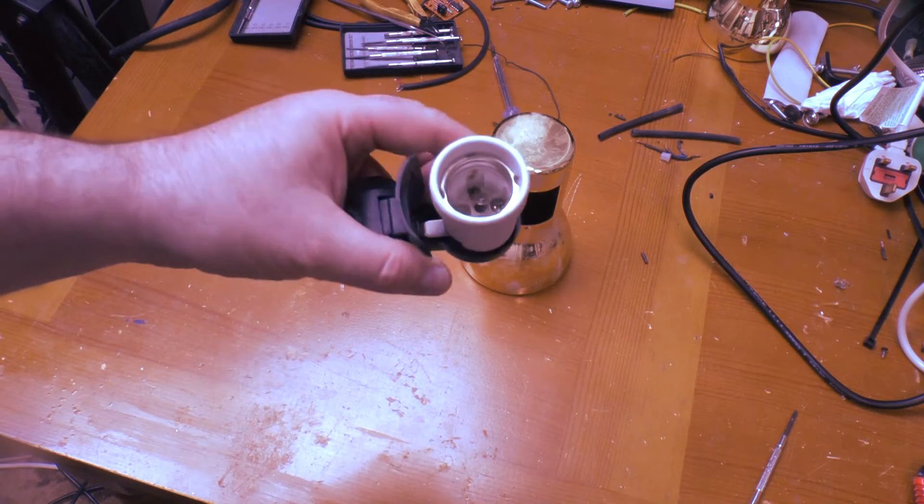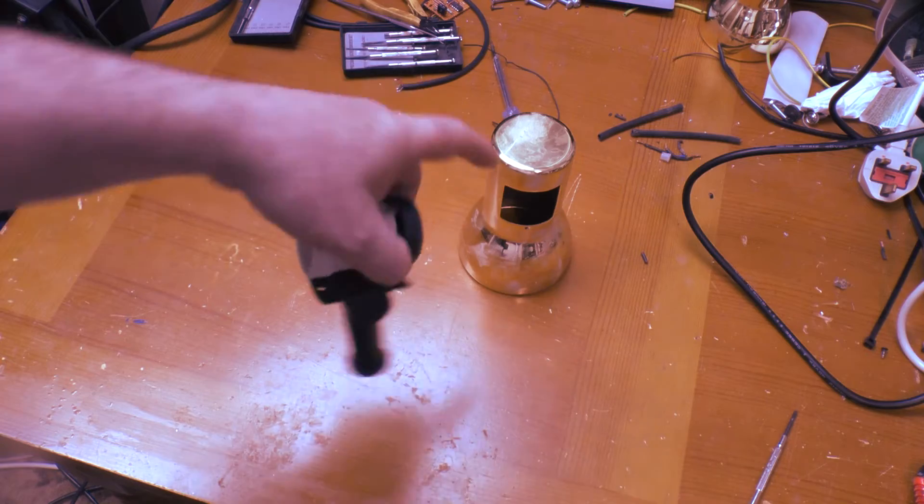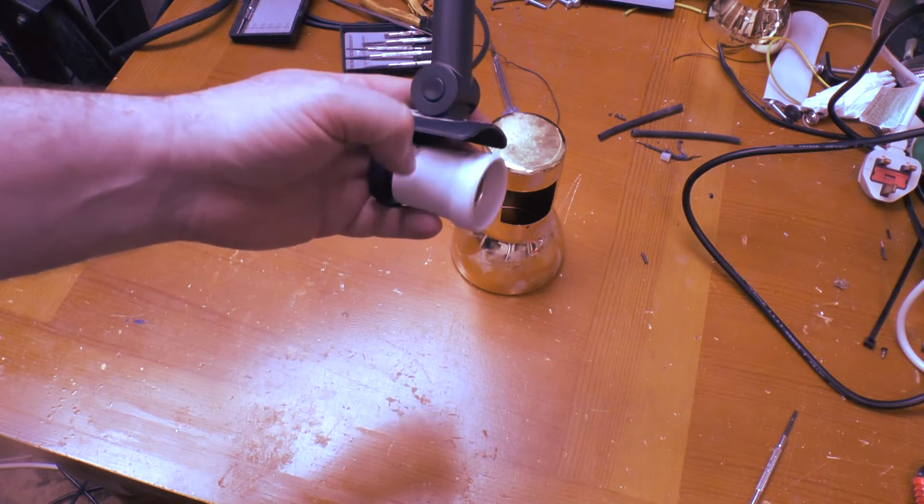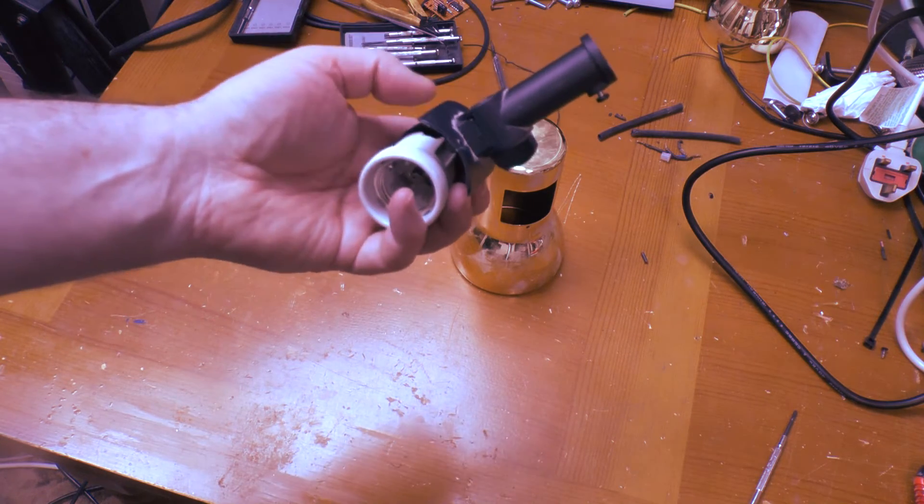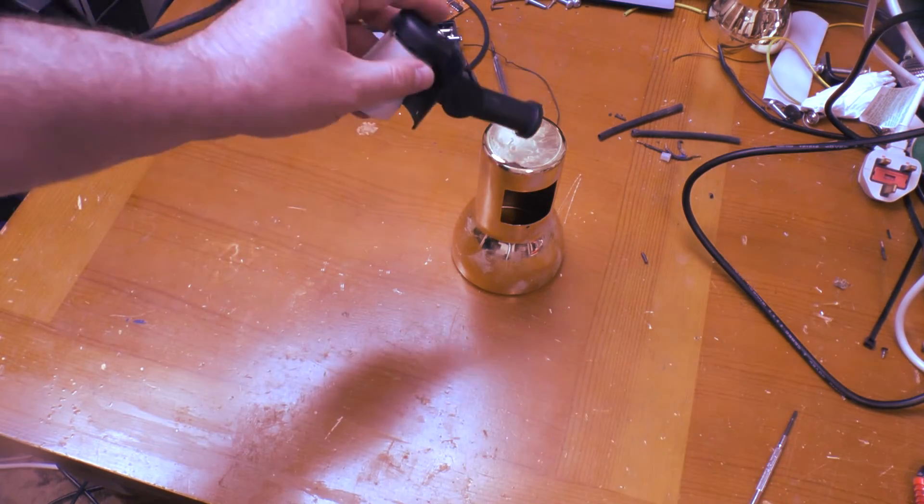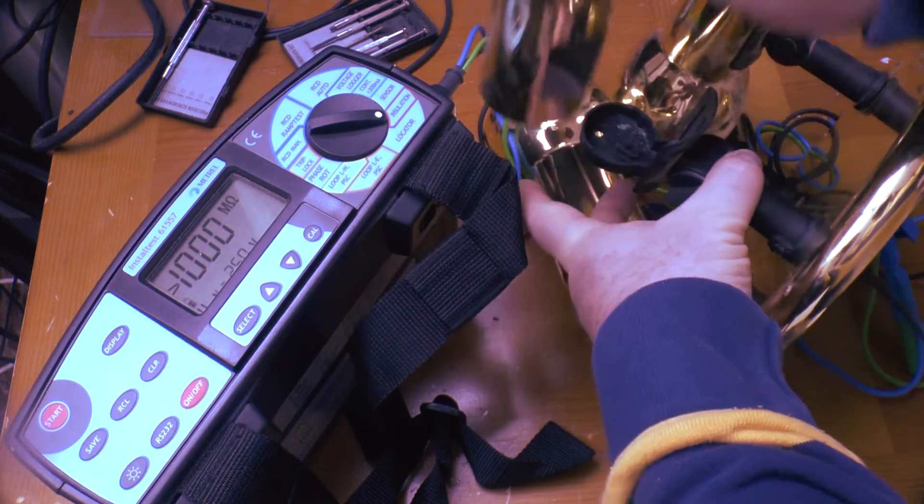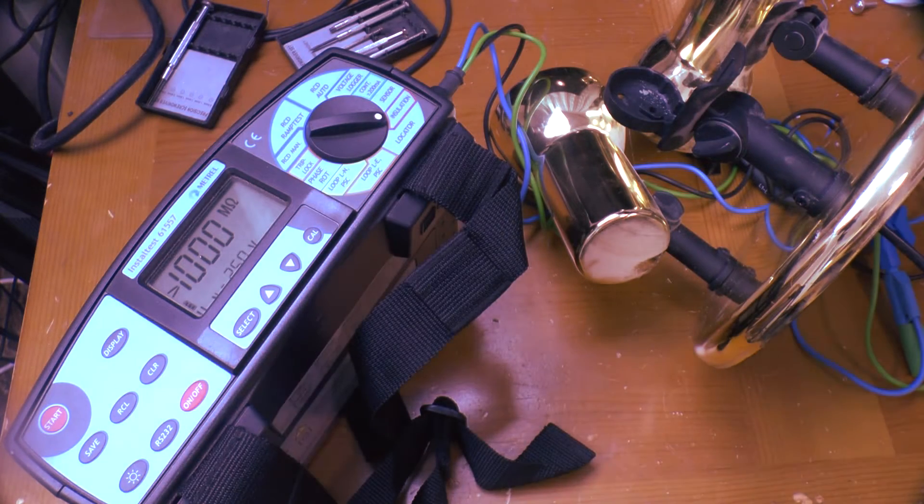Here's the partially reassembled fitting. The mounting bracket at the back is mounted on plastic so it has no contact with the metal shroud. That's actually screwed through on a mounting screw down there. But does that then permit the shroud to be fitted with no earth connection? If the wire came clean out of the terminal, it is possible that rotating the spotlight on its base could bring the end of the wire into contact with the shroud. Does that mean then that this doesn't need to be earthed? Is that sufficiently insulated to not need earthing? I don't know. I'm not the expert in that matter.